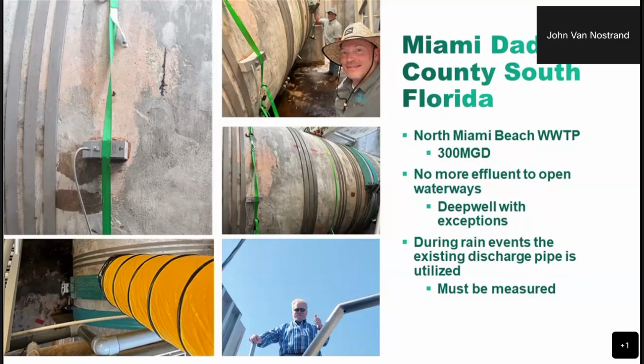They have to measure this because this is their overflow after the deep well. If they're unable to keep up with the flow going into the deep well, which is about 1,800 feet into the ground, then they'll use the old discharge going to Biscayne Bay through this large pipe. To install a Magmeter in this would have been a huge undertaking, and we were able to clamp our transducers on the outside just using a strap.